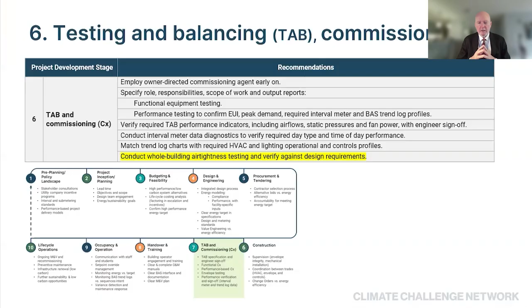Testing and balancing, the TAB reports that, again, we find too often get shelved. If they get submitted, they get shelved. They are your best friend. It's like an X-ray. It's showing you what's working, what's not working, where things get fixed. We'll look at that in just a moment. Because we've got interval metering, the diagnostics we can pull out of that during commissioning means you can validate the required performance, not just overall, but at every time of day, at every day type over the course of the year. And just coming back again to the air tightness testing that we're recommending as being a key part. And again, we thank our friends in Nova Scotia for bringing that to our attention. Next slide, please.